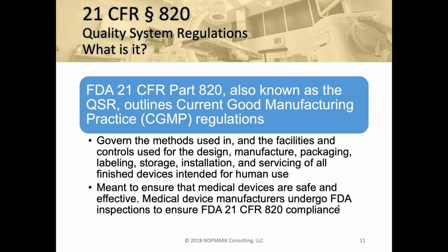So if we now shift to the US regulations, the big regulation that covers software from a medical device manufacturer standpoint is called 21 CFR Part 820. Sometimes you'll see this abbreviated as the QSR, the Quality System Regulation. It covers a lot of stuff. It covers everything that you do, not only the design, but the manufacturing, and how you handle customer complaints.